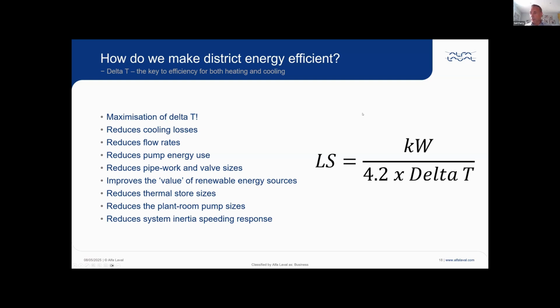And the reason that is incredibly important, and more important than most people realize, is because it allows you to reduce diameters of pipe, valve diameters, fittings diameters. So you're reducing capex on the system. It can reduce the size of your thermal stores. It certainly reduces the size of your pump, and that has an impact on pump energy use. And because pumps operate on the laws of affinity, for every 50% drop in flow rate, your electrical demand drops from 100% to just 12%. So massive pump saving from reducing that flow rate. So there are many capex and opex benefits in increasing the delta T. And that has an impact on system inertia, response times, and all these things. So they all add together and they all compound each other.